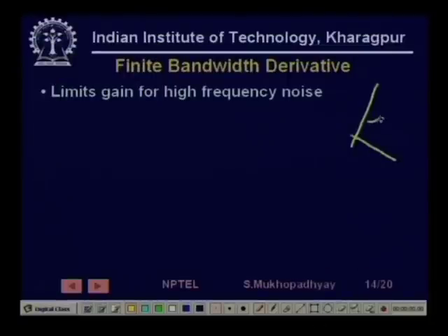So, the turbulence induces frequencies which are much higher than the average volumetric flow rate. While the average volumetric flow rate may be varying like this, the signal that you will get from the sensor may induce very high frequency components. So, these signals are actually due to the turbulence. So, this gives a noise, right.